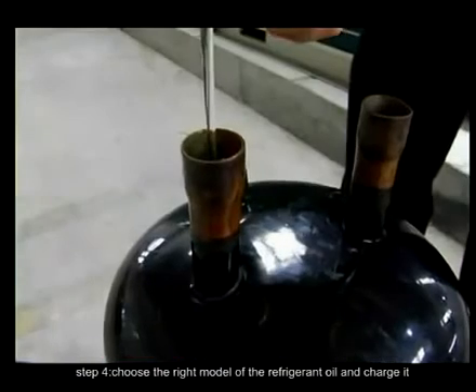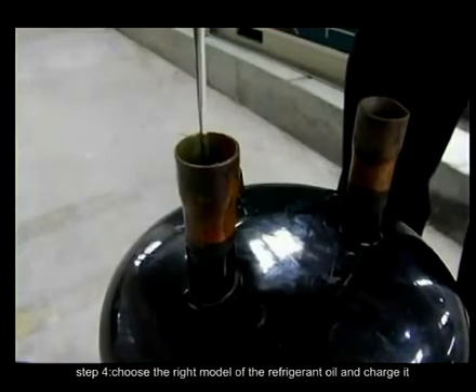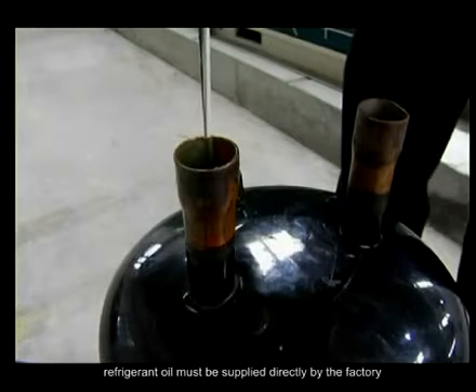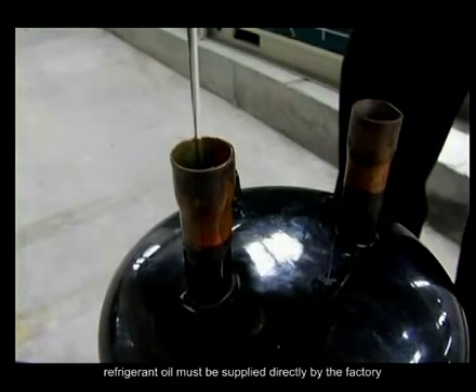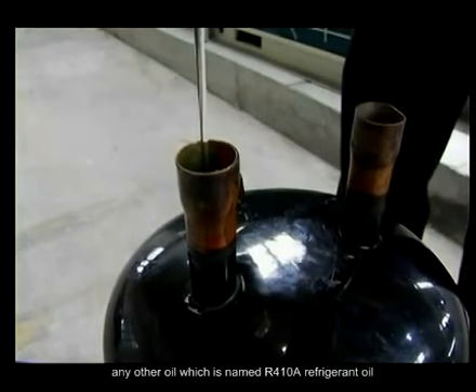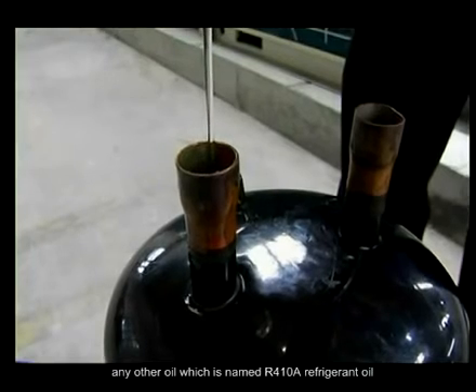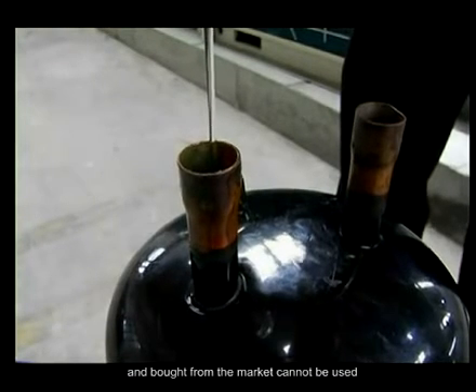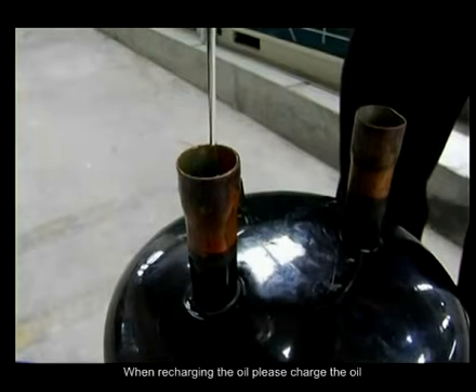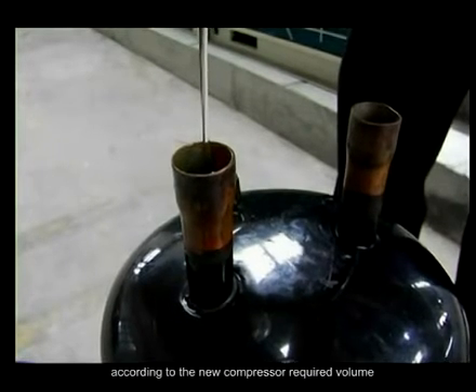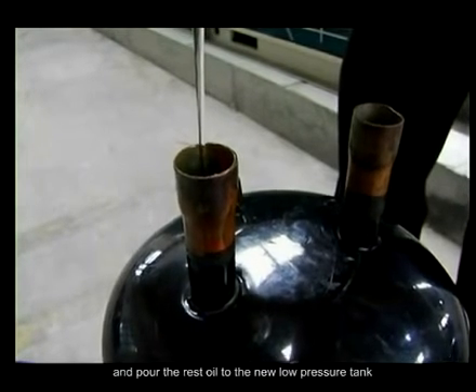Step 4. Choose the right model of refrigerant oil and charge it. Refrigerant oil must be supplied directly by the factory. Any other oil named R410A refrigerant oil and bought from the market cannot be used. When recharging, charge the oil according to the volume required by the new compressor and pour the rest of the oil into the new low pressure tank.